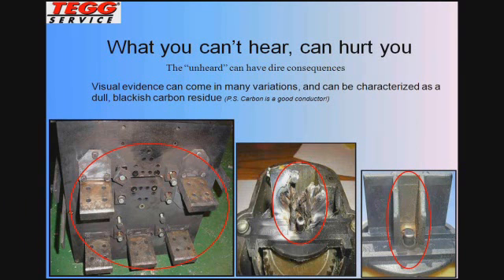The problem with carbon trails here is it's a very good conductor. Motor brushes and things of that nature are made from carbon. They conduct electricity very well. If the buildup gets to the extent where it can bridge the path to ground, you have a flashover. And this is what we want to try and prevent. Fortunately, on this circuit breaker right here, we were able to catch it before it turned into full-blown arcing and make the repairs that were necessary.